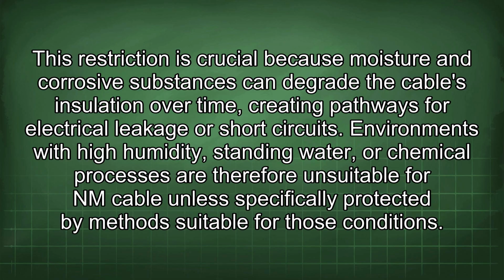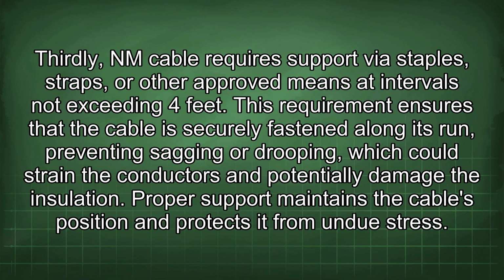Environments with high humidity, standing water, or chemical processes are therefore unsuitable for NM cable unless specifically protected by methods suitable for those conditions. Thirdly, NM cable requires support via staples, straps, or other approved means at intervals not exceeding 4 feet. This requirement ensures that the cable is securely fastened along its run, preventing sagging or drooping, which could strain the conductors and potentially damage the insulation. Proper support maintains the cable's position and protects it from undue stress.